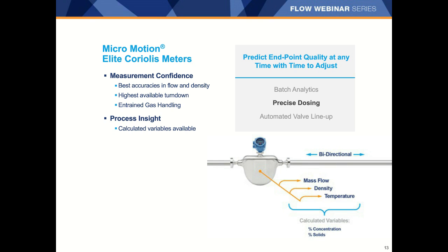The Elite and F-Series meters can operate with an uncertainty contribution of less than 1% with shorter batch times. And the Micro Motion meters are proven to handle entrained gas better than any Coriolis meter on the market because the tube vibration frequency allows for better performance under those conditions.